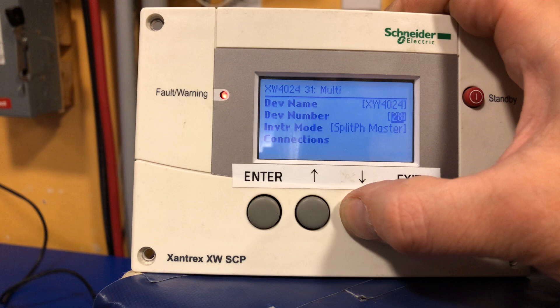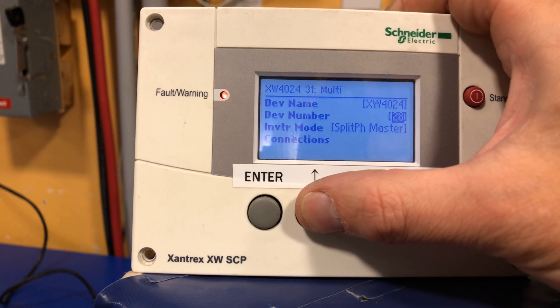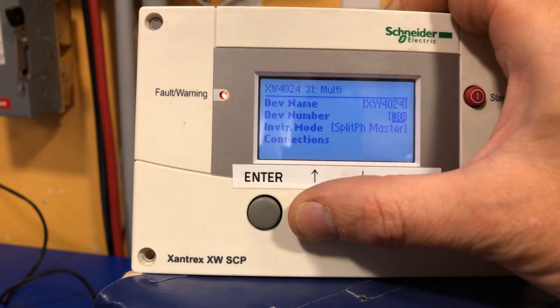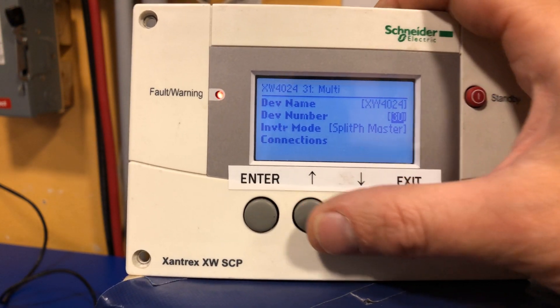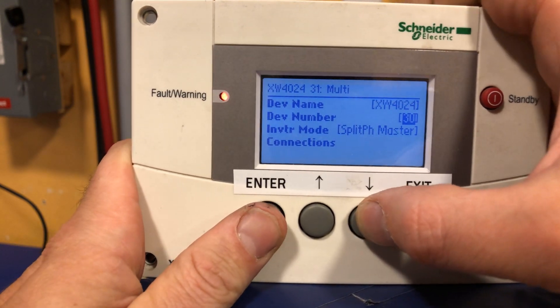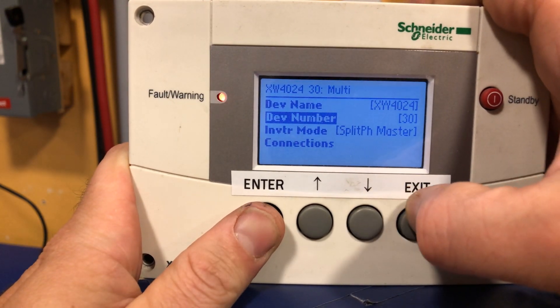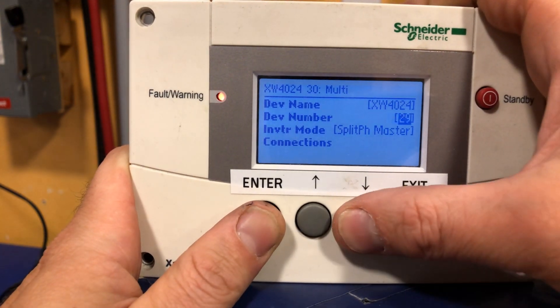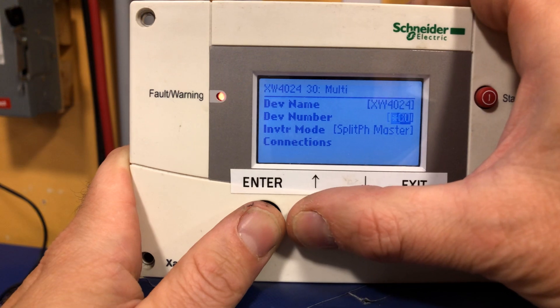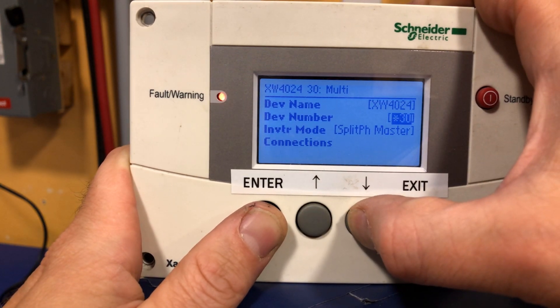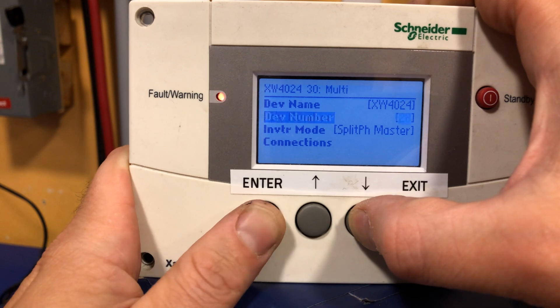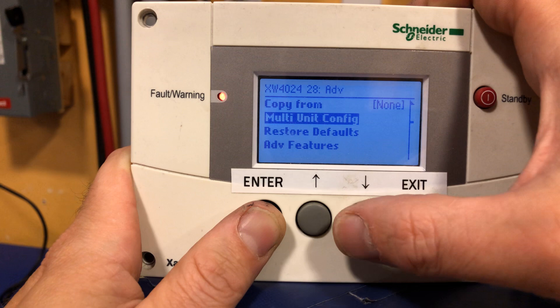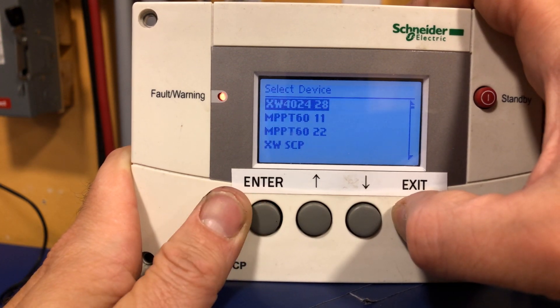I recommend putting the inverters as lower numbers and then charge controllers higher. Use groups of 10 — group them however you want, be creative. Let's come up with a new scheme: inverters at 30. We can see it just took that unique ID number. Let's change it to 28 — there it is, it says 4024 device number 28. Exit back to the list of devices.